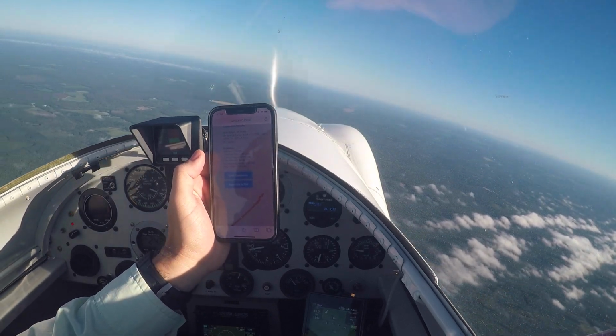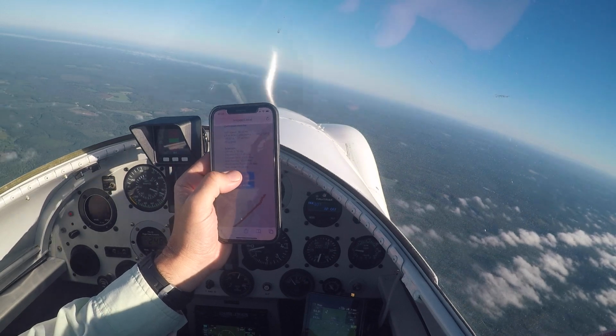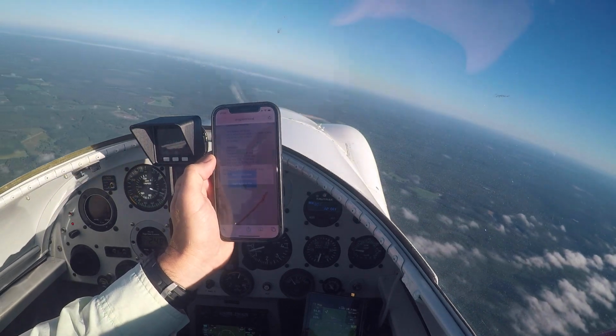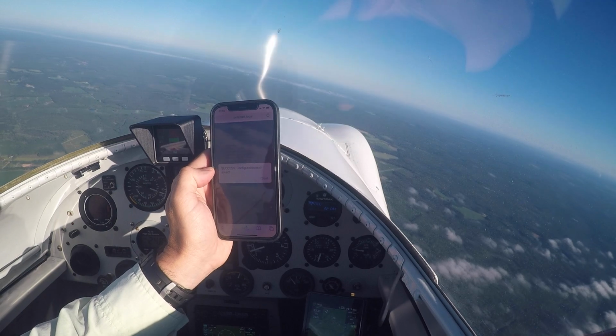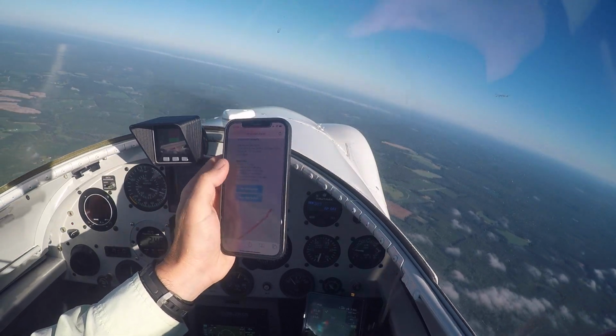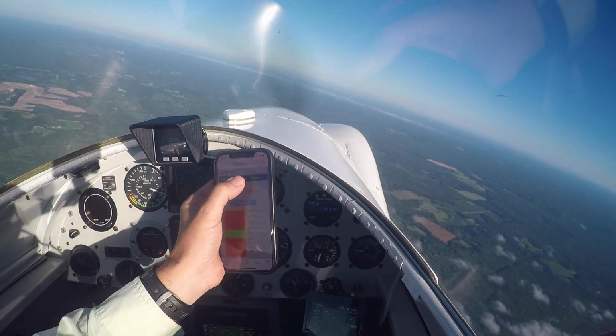And then the very last thing I'm going to do is save the calibration. Once I save the calibration, it's going to input it and see success. Calibration was saved, closed, and that calibration now is in flap curve 1.